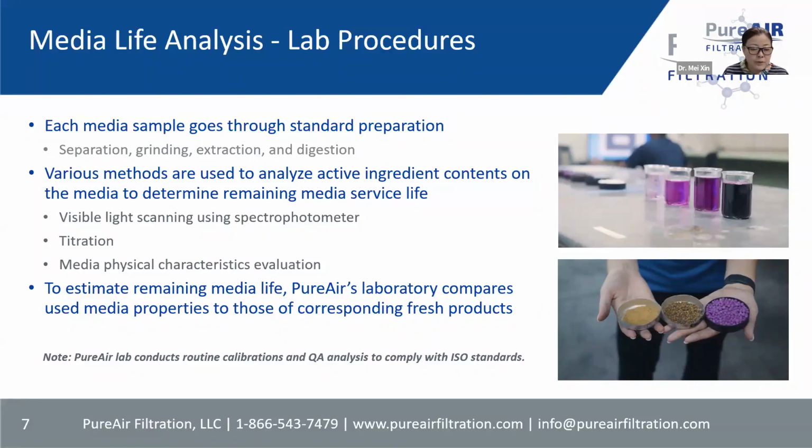And as I mentioned earlier, to estimate the remaining media life, we compare the media sample results against the fresh products.